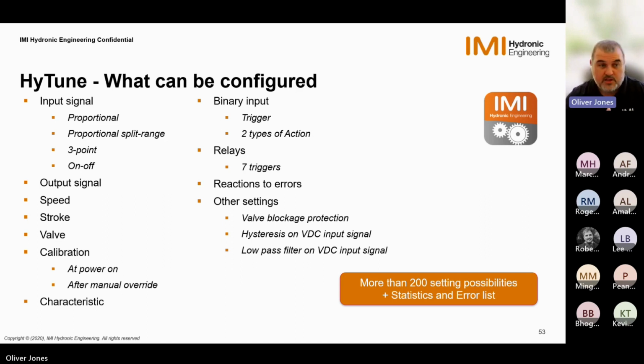By picking the valves on the next one, we can see what our maximum and minimum flow rates are through that valve, and then we can set the stroke so we can deliver the amount of flow rate that we want through that valve specifically. We can also force calibration and change the characteristics. So as I said before, the Compact P is a linear valve. So out of the box, the characteristic is linear on the Slider 160. So we can then change that to an EQM so it works with the linear valve to give you as good control as possible through a linear valve.